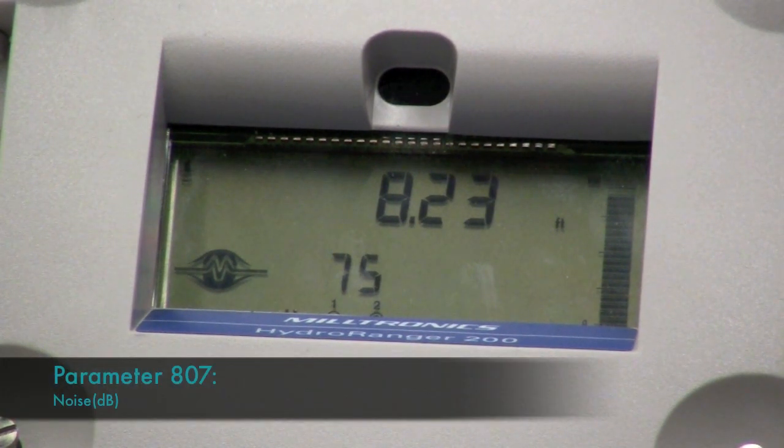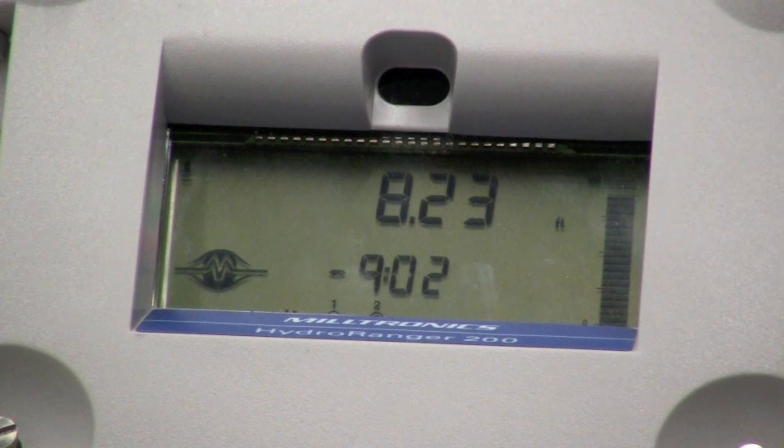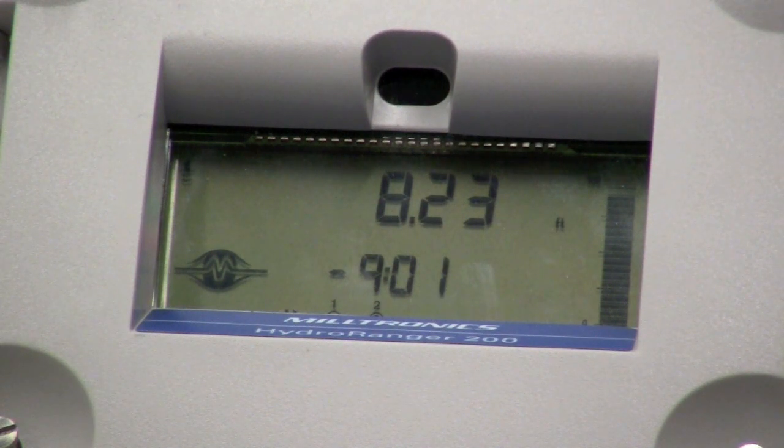Parameter 807 displays noise in dB. The two noise numbers displayed are average followed by peak. The noise may be acoustic or electrical in nature. Average noise is generally more important than peak noise. Any average noise greater than 20 dB may be a cause for concern.